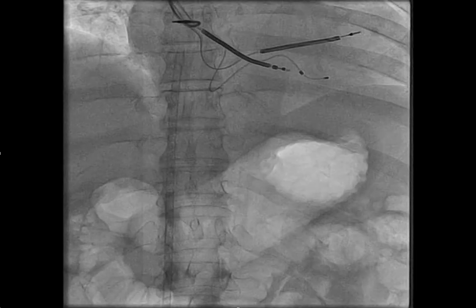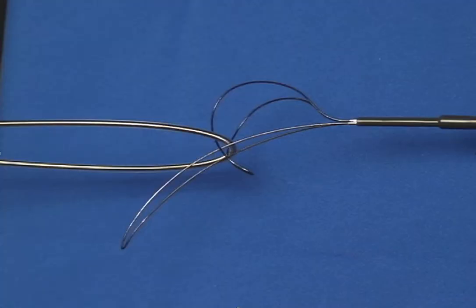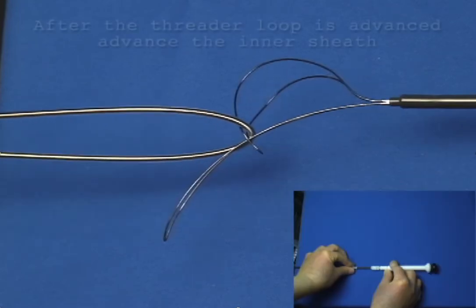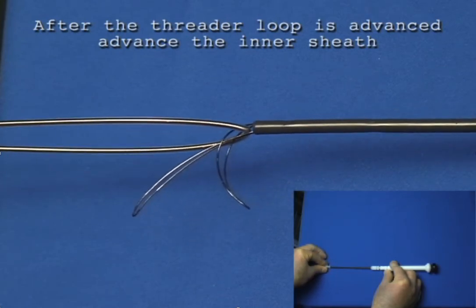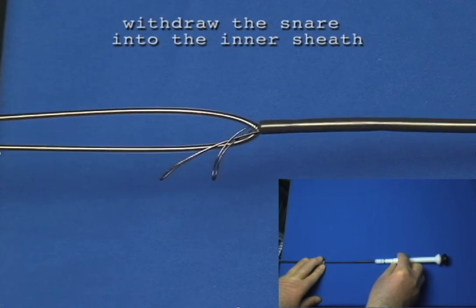And that way you can aim which way you want to go by using the outer sheath and not the curved inner sheath. And so you can see what we've done is we've successfully grabbed it. And once we've extended the threader loop and we have it, now we need to lock it in place. And to lock it in place, you extend the inner sheath.